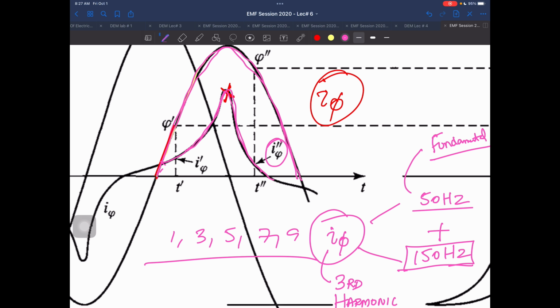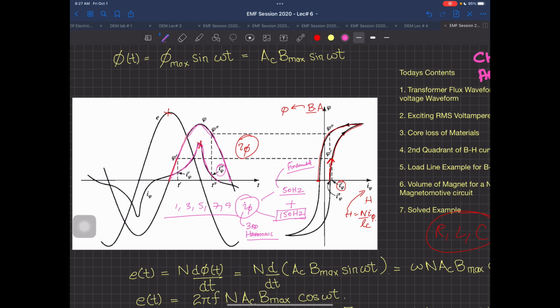Just for now, if your fan is being provided 50 hertz, it is going to have a speed given by 120F by P. I'm giving this equation quickly, but just to understand: you are giving a 50 hertz supply and the number of poles in this machine is supposedly 4. Put in the value, you will get 1500 RPM. And behind this fan, you have 1500 RPM written as its speed.